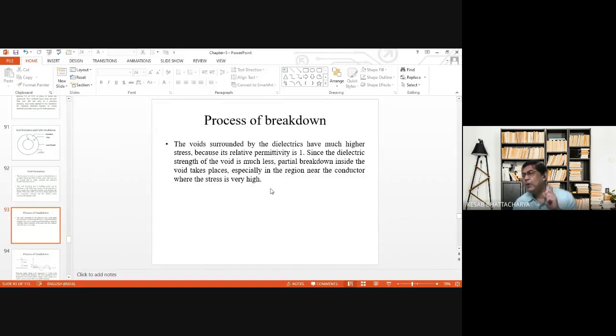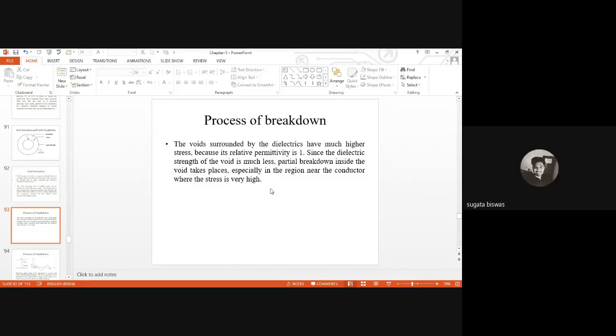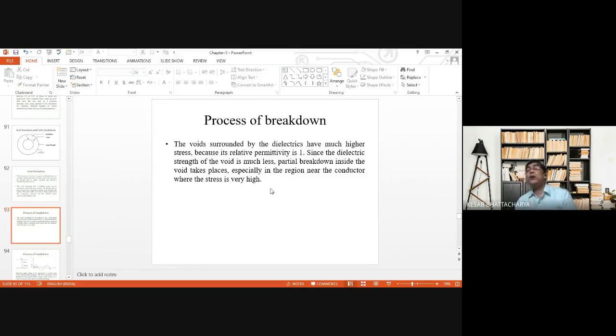Now, the relative permittivity of the void is 1, but the relative permittivity of the insulating material is more than 1, maybe 2, 2.3, 2.5, like this. Therefore, for the same applied voltage, the magnitude of the electric field across the void will be much more than that in the insulating material. Is that point clear? Yes, sir. Therefore, it may so happen that even at the operating voltage level, the stress developed may not cause any damage to the solid insulating material, but it may cause ionization or breakdown of the void.